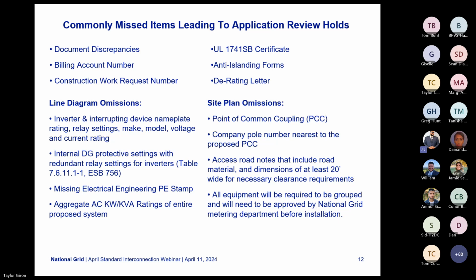Missing UL certificates, anti-islanding forms, or curtailment letters will also lead to holds. On the one-line diagram specifically, it needs to show inverter and interrupting device nameplate ratings, relay settings, make and model, voltage, current ratings, DG protective settings, and everything else laid out in the checklist.